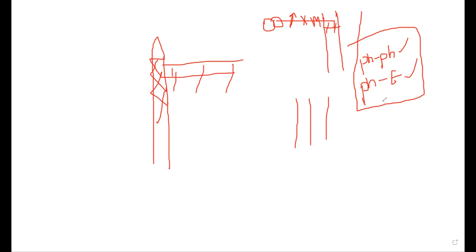These phase to phase and phase to earth clearances depend upon the basic lightning impulse level and basic switching impulse level of my substation. These phase to phase and phase to earth clearances depend upon my BIL and BSL levels of my substation.